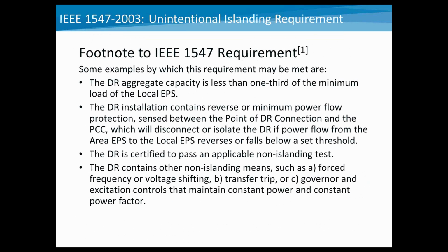Okay, so in addition to the requirement, there's a footnote in 1547, and the footnote is very important to read because it gives some suggestions on how to meet the requirement. So, for example, you're able to meet the requirement if your DR capacity is less than one-third of the minimum load of the electric power system, so the DR is small in relationship to the local load. If the DR contains minimum or reverse power flow protection, if the DR is certified to pass an applicable non-islanding test, and if the DR contains other non-islanding means, such as forced voltage or frequency shifting, transfer trip, or governor excitation control. And we'll talk a little bit more about these in a couple of slides here.